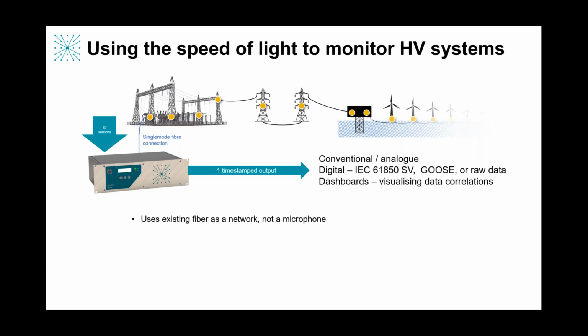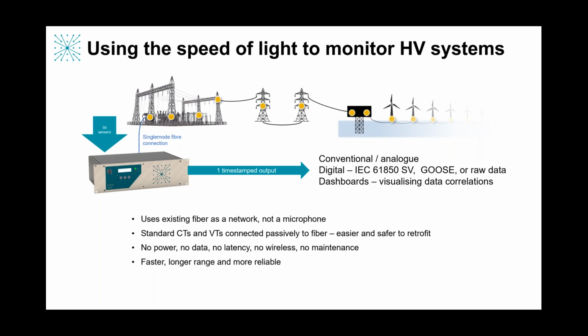This is electrical and mechanical sensing, which is using the fiber to bring the signal back very quickly and very fast. In fact, we use industry standard current transformers and voltage transducers, CTs and VTs that you'd see in any substation around the world, but we figured out how to make them passive, and they connect through the fiber, so it's very easy and safe to retrofit them. And it means at any location that you want to measure something, there's no data, there's no latency, there's no wireless signal, there's no maintenance of batteries or equipment, because there's no power.